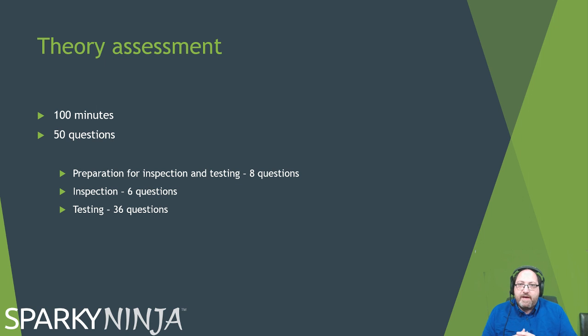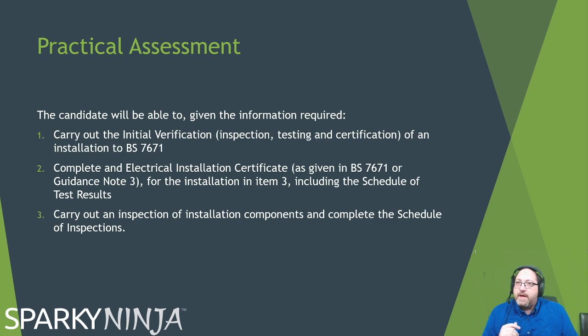Of the assessment you have there, many questions come from the testing application side itself. I'll give you a good idea as to what kind of questions there will be. The practical requires the candidate to carry out a full initial verification. This includes inspection, testing and the certification of an installation to the current version of the regulations. You'll be provided with the installation and all the documentation by your assessor, but you must carry out a safe and in sequence initial verification. You must complete the certification properly, and you must complete the schedule of inspections and the schedule of test results properly. I think it's like 2 hours for that. I could be wrong.